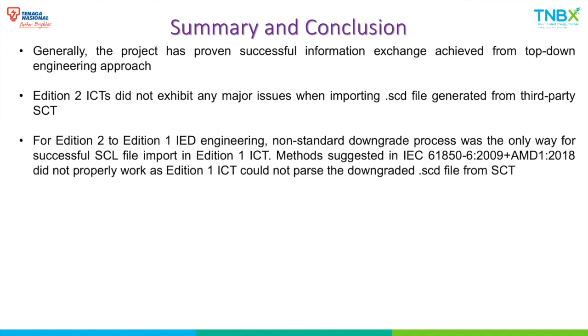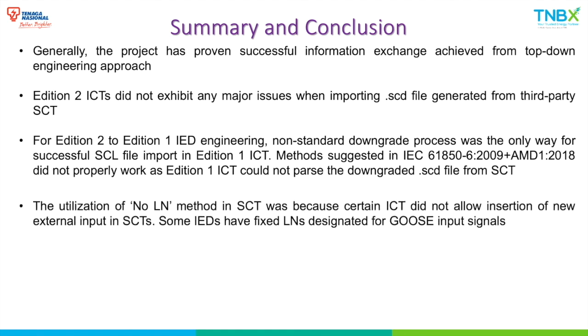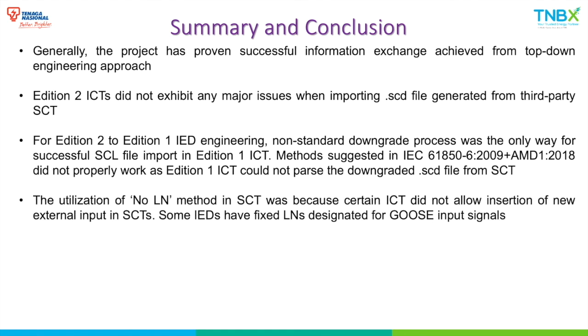As mentioned, for Edition 2 to Edition 1 IED engineering, the non-standard downgrade process was the only way for successful SCL file import into the Edition 1 ICT, but we were only able to configure 2 out of 4 Edition 2 IEDs. We also had to use the no logical node method in the SCT because certain ICTs did not allow insertion of new external input.